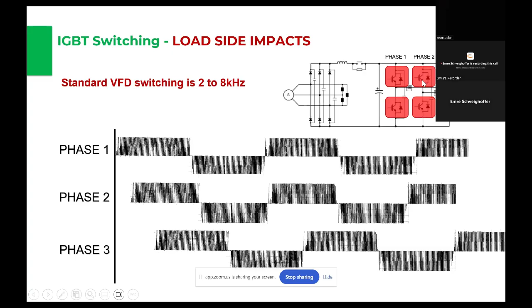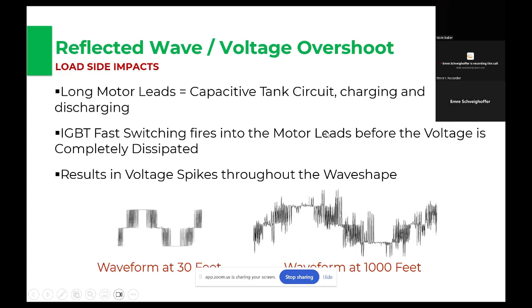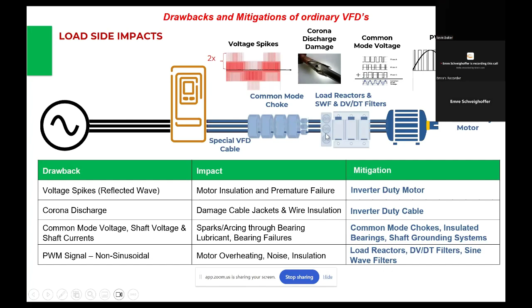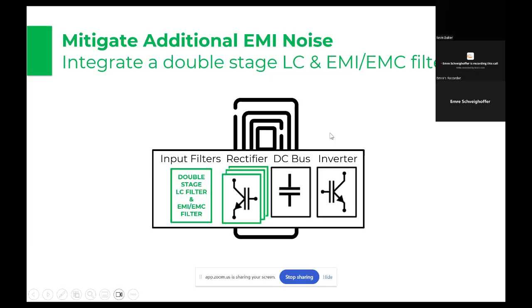What they've done is use something called cascading H bridges, or other types of topologies, to feather in more pairs or more units of IGBTs in order to break down the number of steps you have in creating your sine wave. This one here is pretty raw, it's showing almost like a 6 pulse on the back end. These 2 levels are what's on every drive out there on the market. We're not necessarily the first, since custom made product exists, but we're the first to mass produce this multiple layer, multiple level switch tandem approach, which lets you contribute to a much better sine wave.